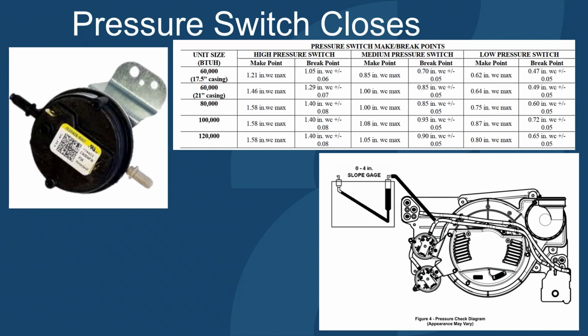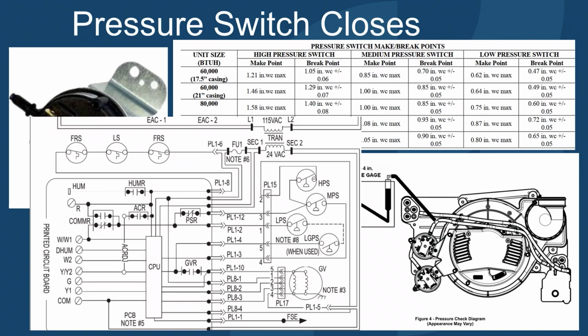The next thing that will happen will be the pressure switch closes. Furnaces can have up to 3 pressure switches: a high pressure switch, a medium pressure switch, and a low pressure switch. The make and break points for these switches can be obtained from the manufacturer, and it is necessary to properly troubleshoot the pressure switch. You will also need a manometer and a T to tap into the pressure switch hosing. You will also need to be able to troubleshoot the pressure switch electrically by checking with an electric meter to see if there is continuity through the switch or not. Checking to see if the switch closes when it's supposed to.